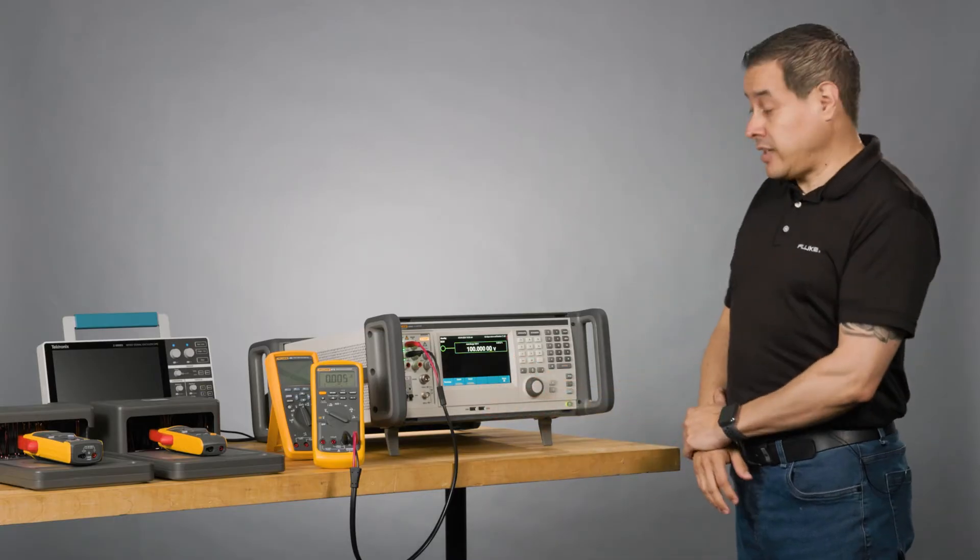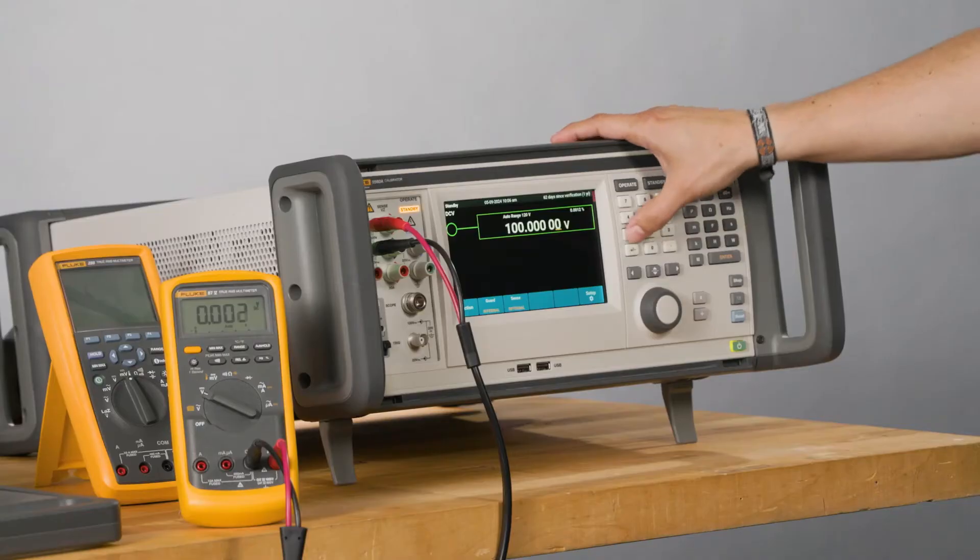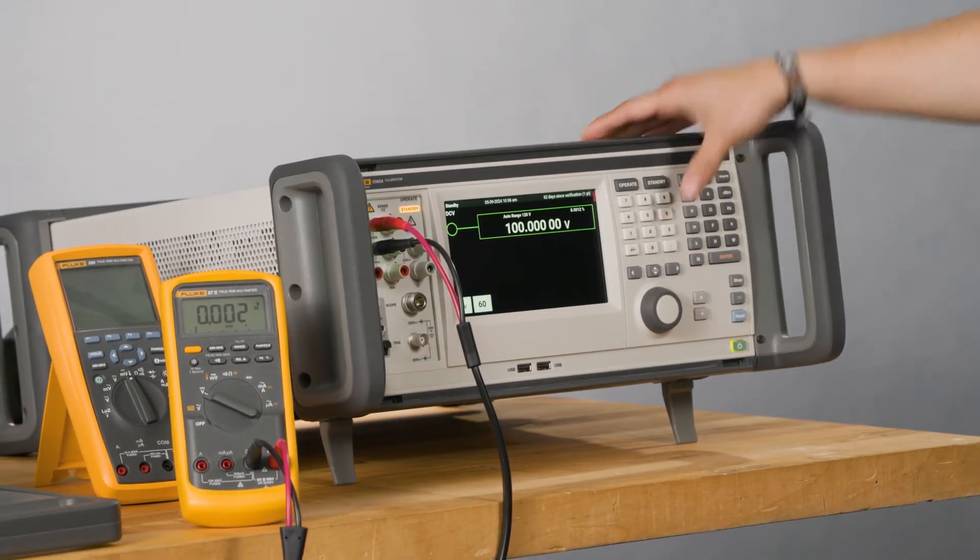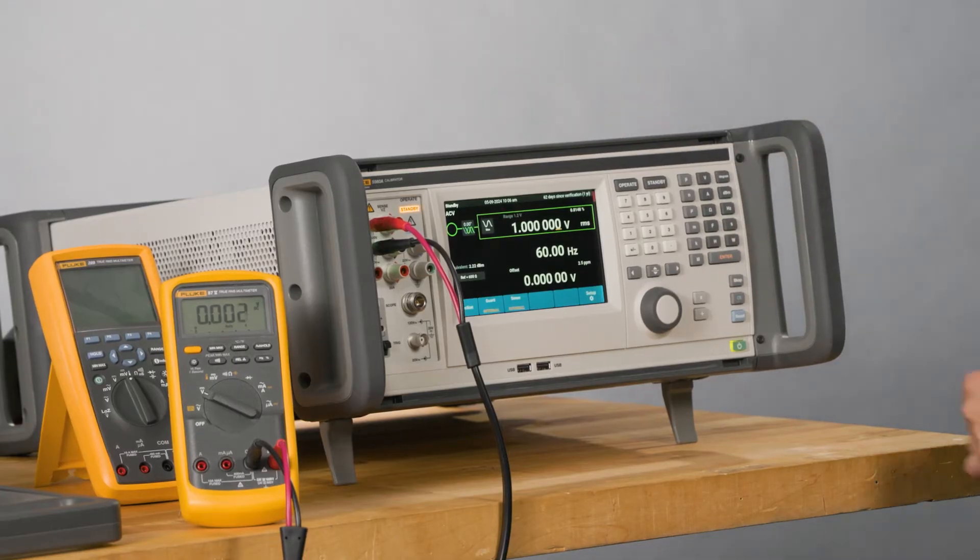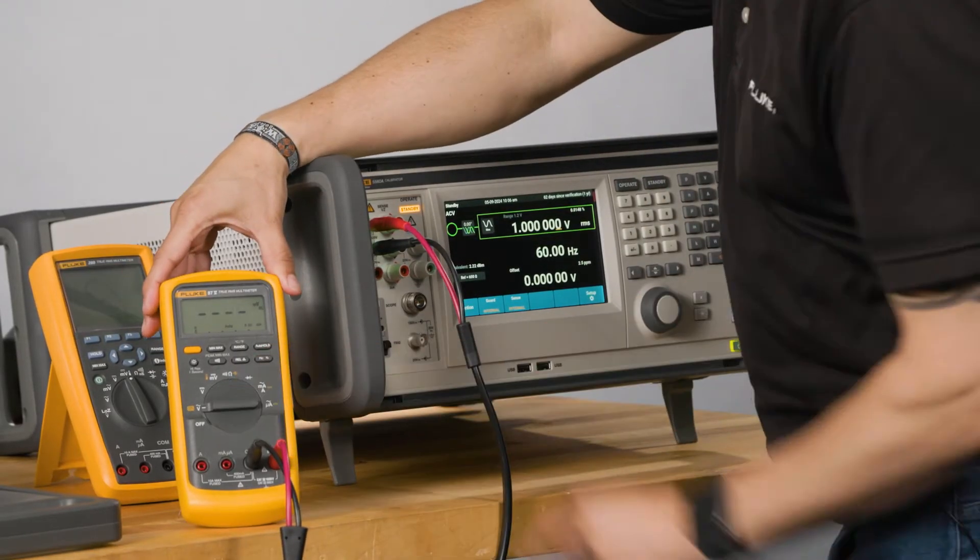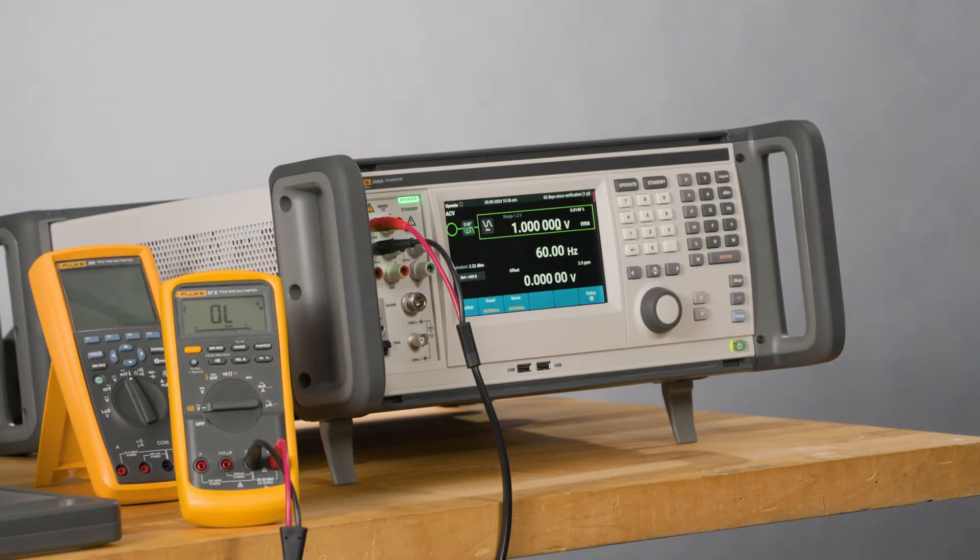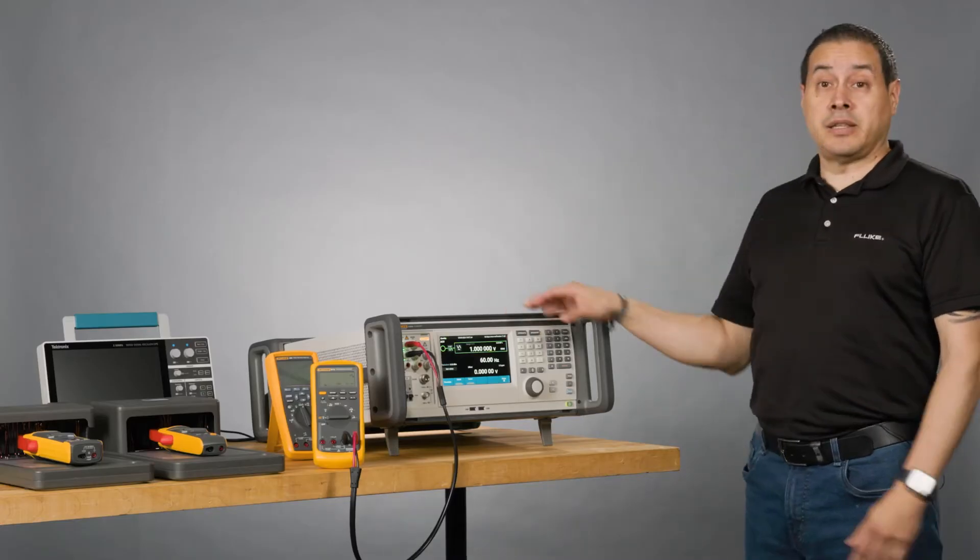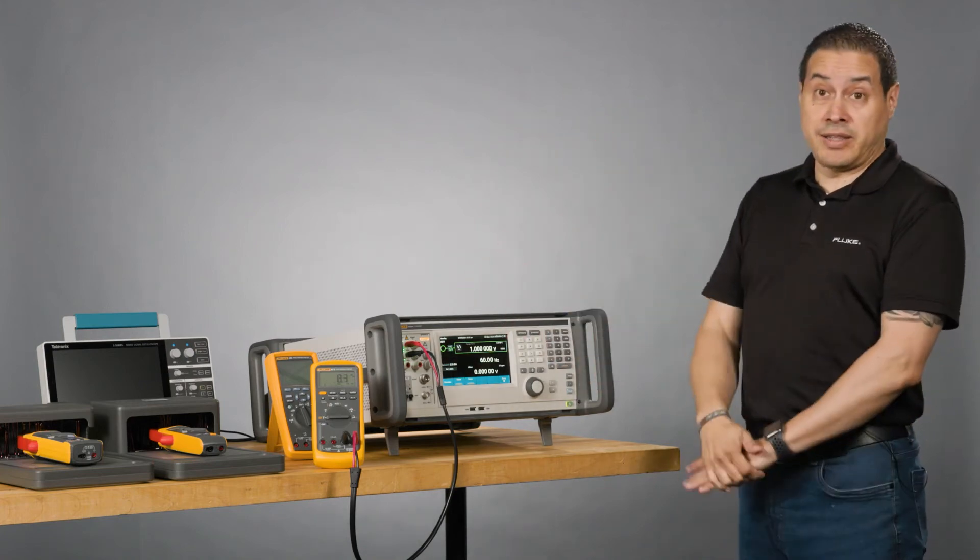Now I'm going to jump to ACV. In this case, I don't need to change the cables. So one volt, 60 hertz. Enter. And then I need to change my knob to ACV. I got one. You need to wait to stabilize. And then same process that I did in DCV. Jump to the calibration point that the manufacturer indicates.